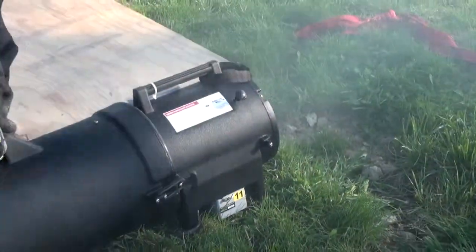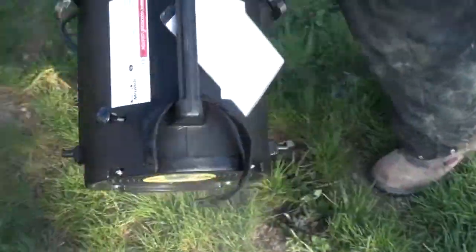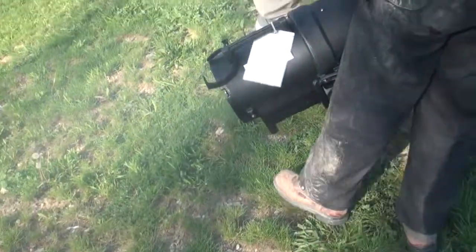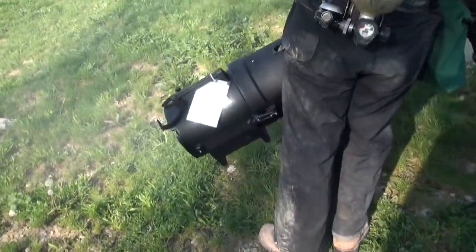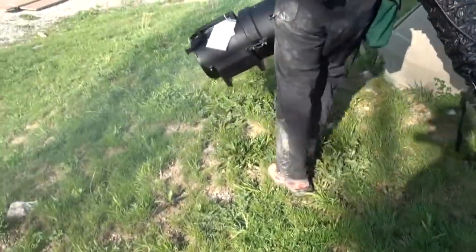So by using negative pressure, we can draw the contaminant out, remembering to place the ductwork within the space in the area of which we expect the product to be, and then keep our blower motor away from the opening so that we can exhaust that contaminant out of the area and keep that area safe to inhabit while we're working.